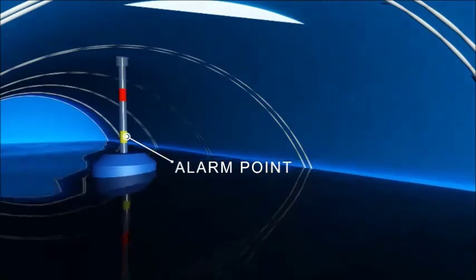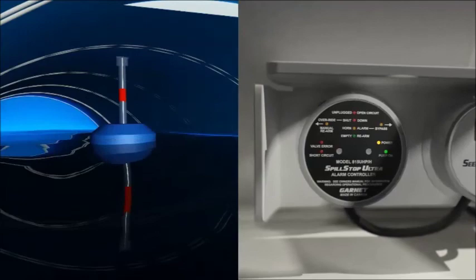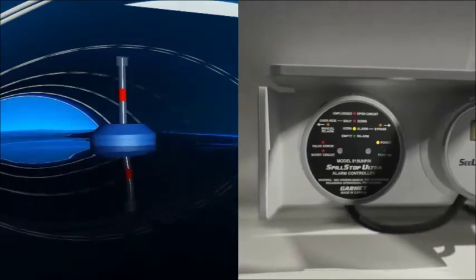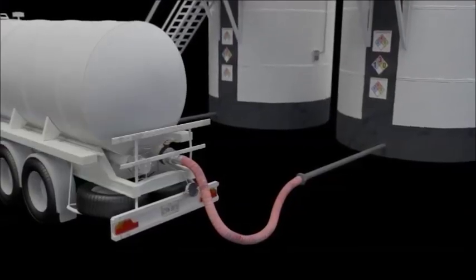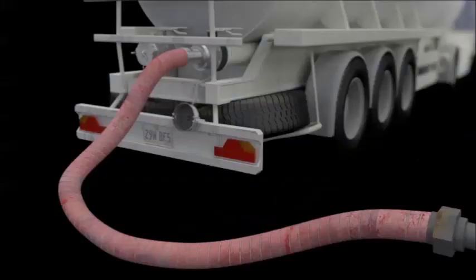The gauge has a programmable alarm point that, when reached by the float, will activate the orange horn alarm indicator on the display, sound an alarm to notify the operator that the tank is full, and shut down the pump.